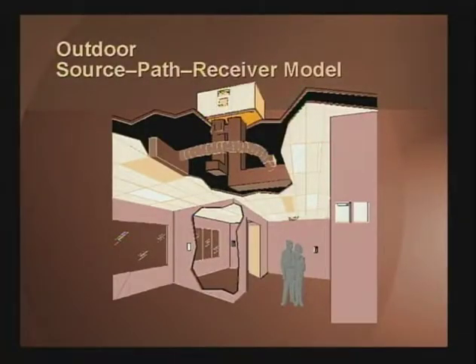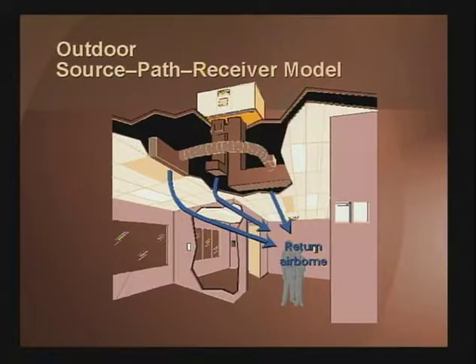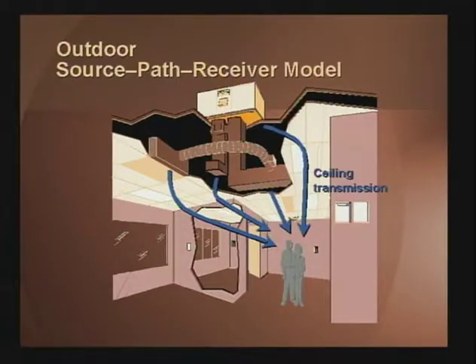We can look at this for another type of application just to show you how this applies to a different piece of equipment. In this case, we'll have a rooftop unit. Again, we're going to have a supply airborne path, sound that comes with the supply air through the diffuser into the space, a supply breakout path. There's a return airborne path. And if you had more return ductwork, you may even have a return breakout path. In this case, the sound that's radiated from the casing of the unit is radiated to the outdoors, but a portion of that sound goes down through the roof and through the ceiling, and that's our ceiling transmission path.